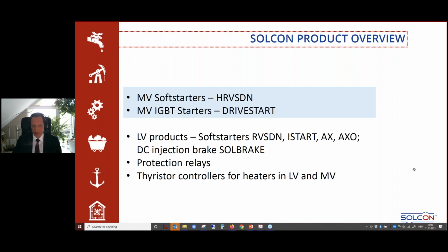Normally, we do not sell these as a single item, sometimes to switchgear vendors, but in most cases, they come along with the soft starters that we are selling into the market. One topic that we are offering in the market is thyristor controllers for heaters in low voltage and medium voltage. And the nice thing here is a heater has a very long time constant. So in order to control the heat in the process, you are switching on, switching off, and on and off. But the vacuum contactors do not like the high frequency switching. So the means of choice here is thyristor controllers for this.